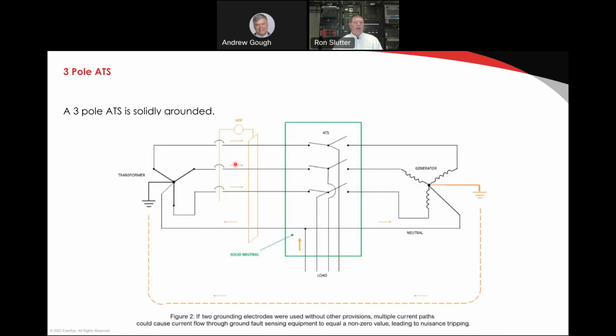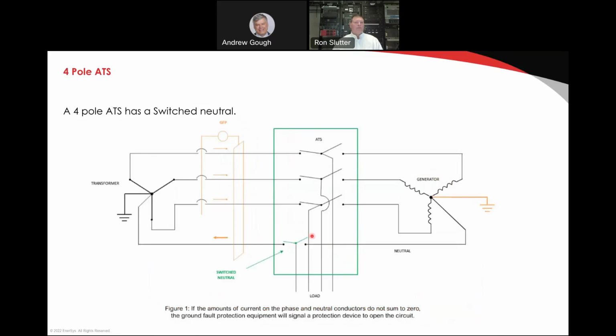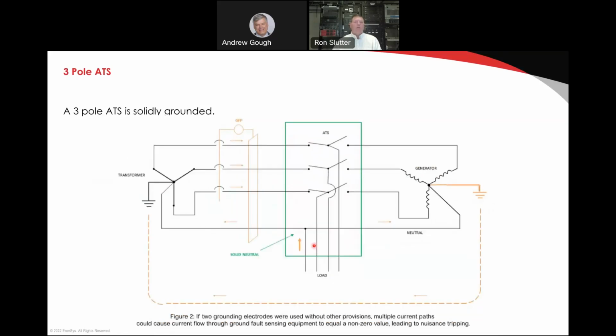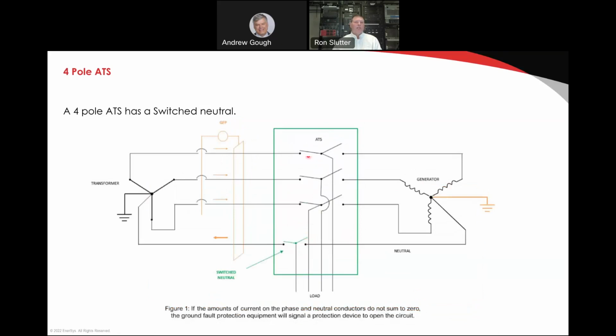Okay? So how do we get out of nuisance trips when we have a solidly grounded ground fault system that we need to install? The way that we do that is we have to install a 4-pole ATS. Notice the difference between this and the 3-pole. The neutral is solidly connected together. We move to the next screen, we can see that this is the 4-pole ATS, where the neutral is also switched between the two sources.